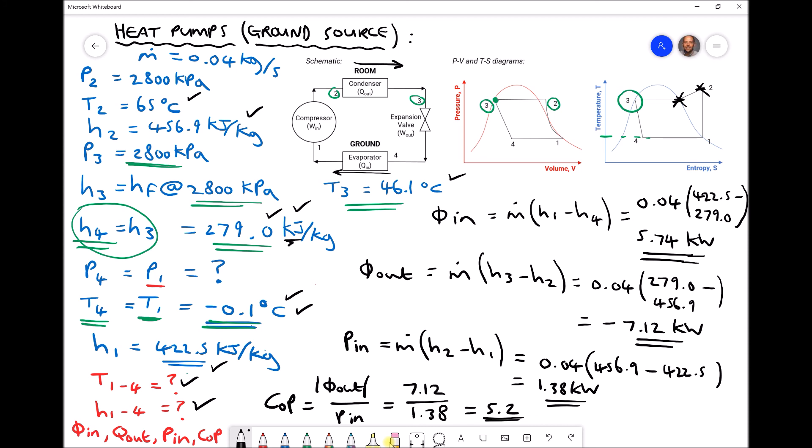Now the coefficient of performance number is so important because it helps us to determine whether the use of a ground source heat pump or an air source heat pump is viable in terms of the cost of running that device. Although here we're getting 5.2 kilowatts of heat for every kilowatt of electricity consumed, the cost of electricity is significantly higher than the cost of gas.